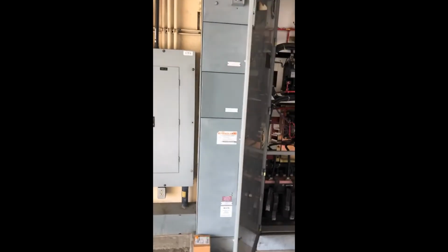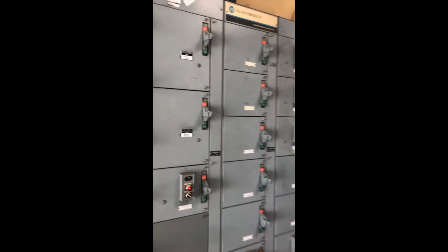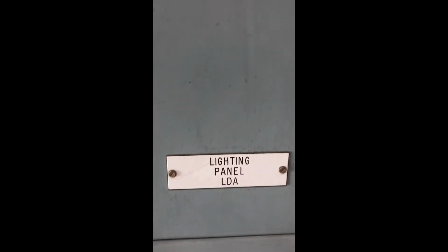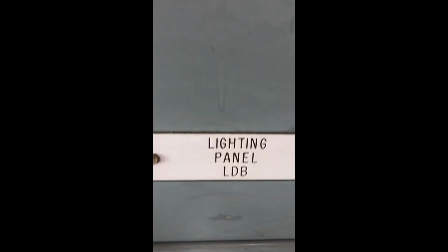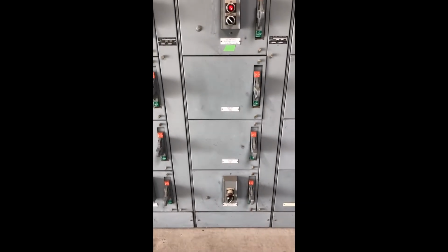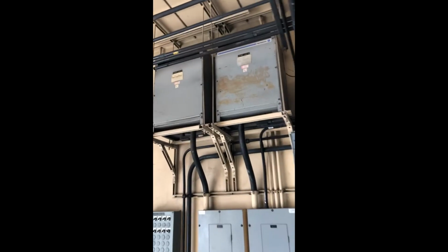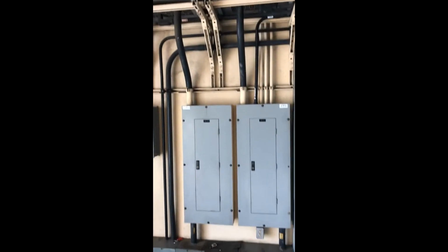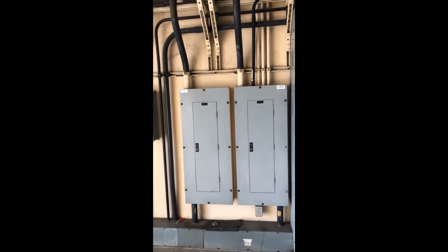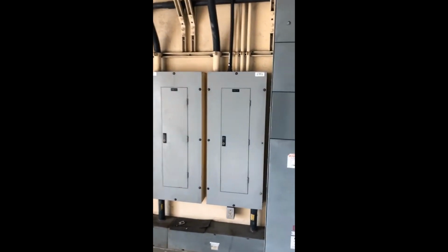They are being fed from probably this panel here. Yeah, so here is that's for one of them, and that's for the other. And that's the 480 volt circuit breaker for the primary side of these lighting transformers. And then on the secondary, these are the distribution panels for all of the single phase power around the plant.